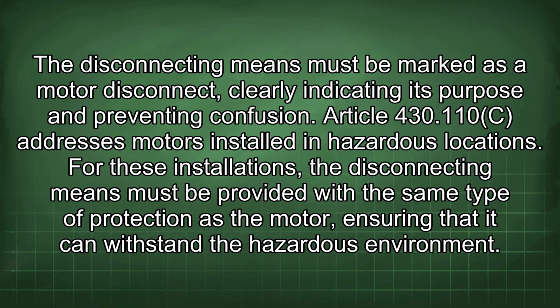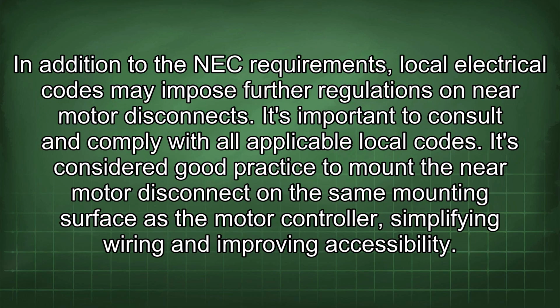Article 430.110c addresses motors installed in hazardous locations. For these installations, the disconnecting means must be provided with the same type of protection as the motor, ensuring that it can withstand the hazardous environment. In addition to the NEC requirements, local electrical codes may impose further regulations on near motor disconnects. It's important to consult and comply with all applicable local codes.